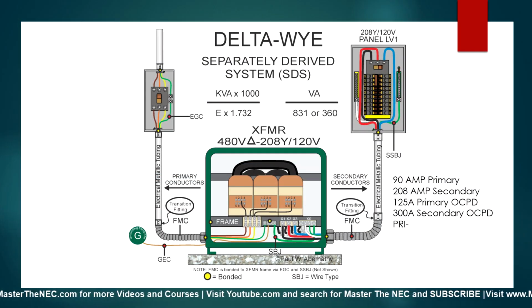So here, since this was a 2, and it's the same application because it's still 350 and it's using the same table, we can deduce that this is actually going to be a 2 as well. So this would be a 2. The system bonding jumper would be a 2 gauge. The supply side bonding jumper would be a 2 gauge because, again, it's all based on these derived conductors. So we've done all that sizing.